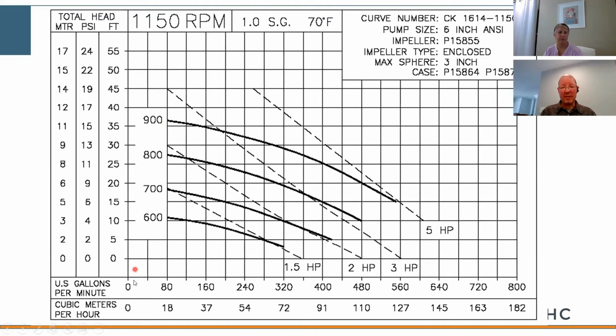One thing you'll see is obviously flow rate down here on the X or horizontal axis. You'll see discharge pressure up here on the vertical or the Y axis. You also see impeller sizes. So 600 is a 6-inch impeller, 900 is a 9-inch impeller. So these are simply impeller lines. And then these diagonals over here are horsepower lines. Okay, so 1.5 horse, 2, all the way up through 5 horse.